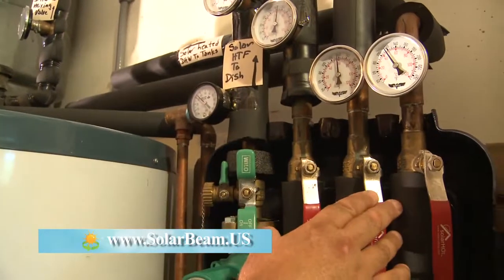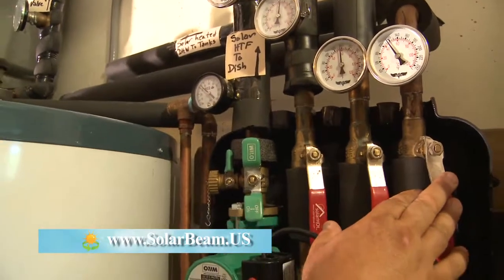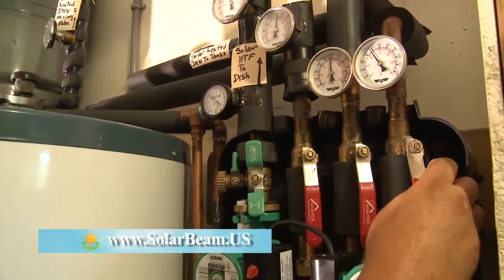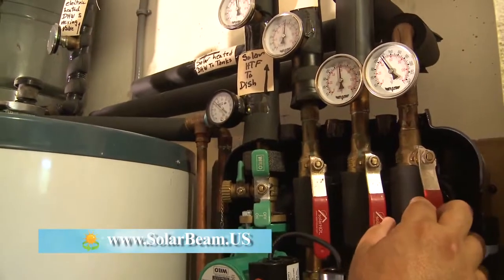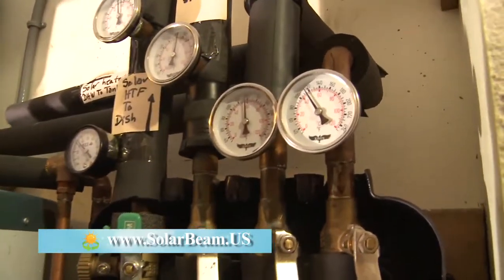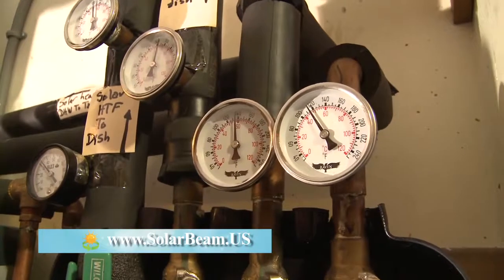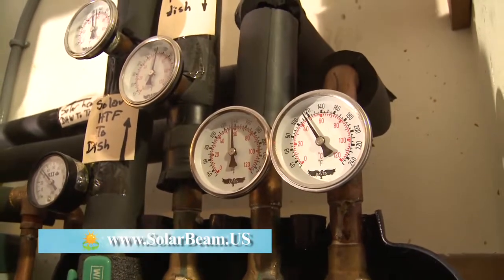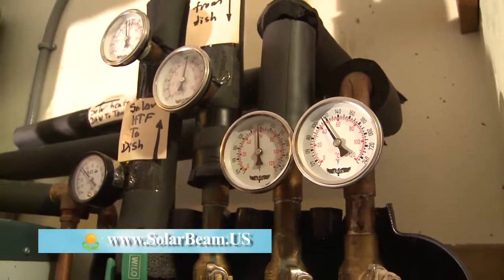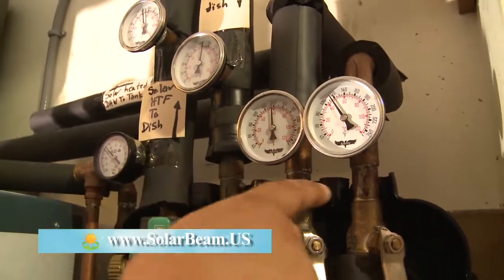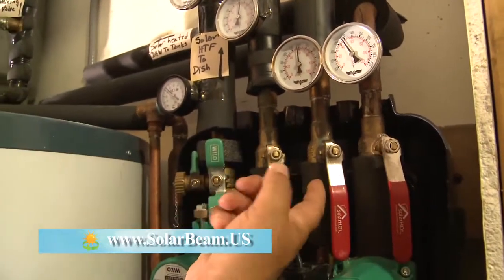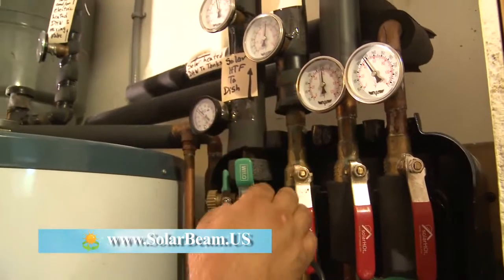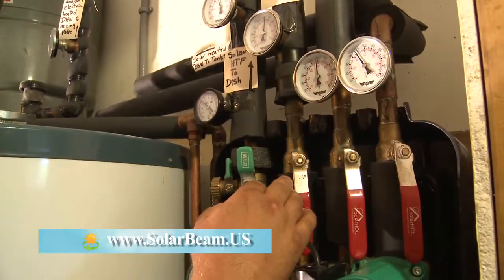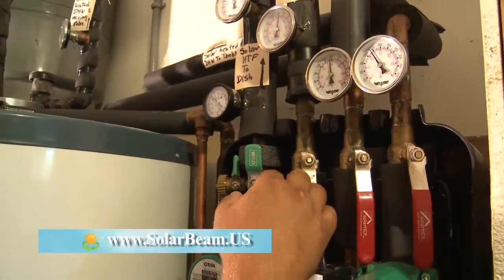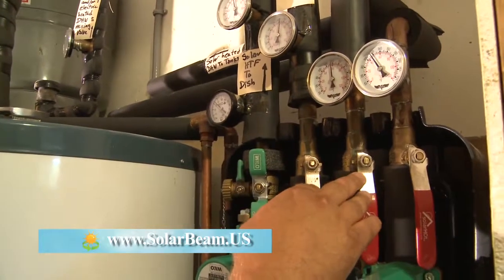As you can see by this, the temperature of the water that's coming in is 125 degrees. If I read that correctly, I'm sorry, 115 degrees. And the temperature after it goes through the heat exchanger, it comes through this pipe, and it's about 138 degrees. So we're picking up about 22 degrees on that alone, right in this area.